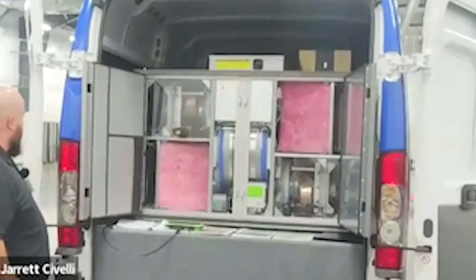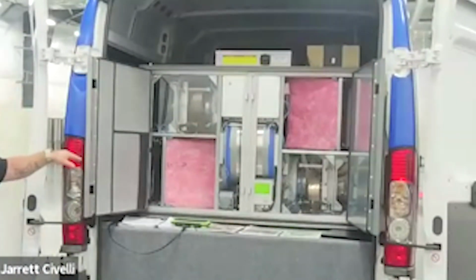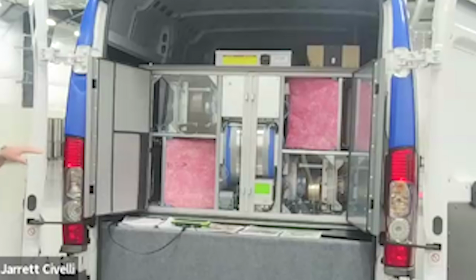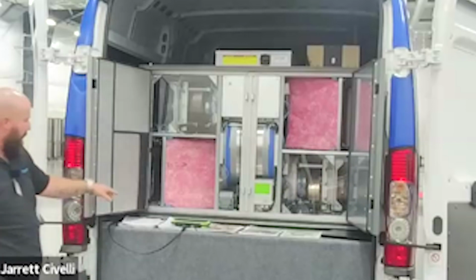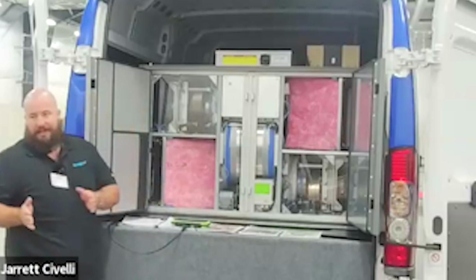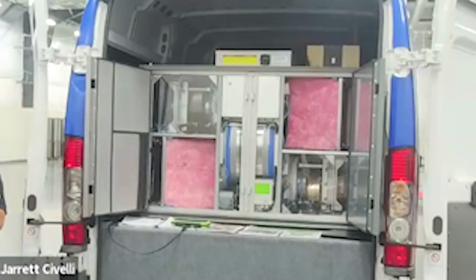So we'll start with outside air coming in. Bottom left-hand corner, we have MERV 13 filters. Swegon has a gasketed filter rack, so each of these two blue handles actually forces that bag filter up against a gasket, so we have minimal leakage. MERV 13, just because it's a higher MERV rating, captures more and protects the wheel from dirt. There is a slot for a 2-inch pre-filter to extend the life of those bag filters. That's up to the customer or the engineer.